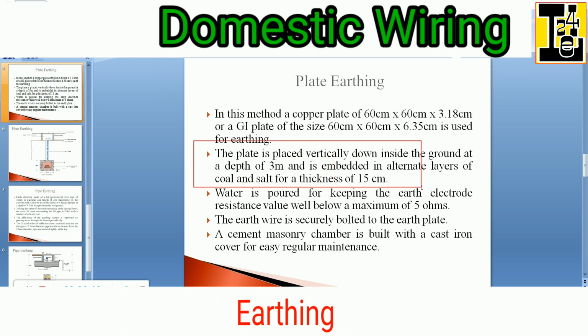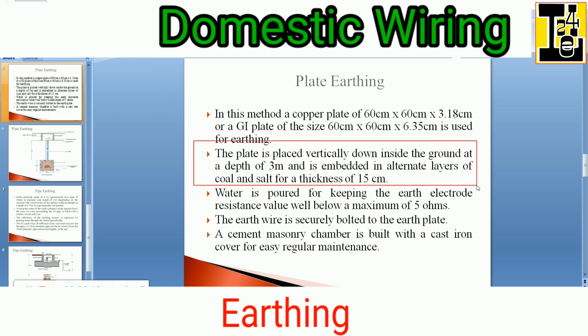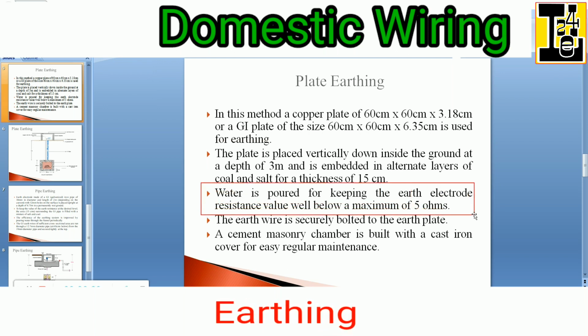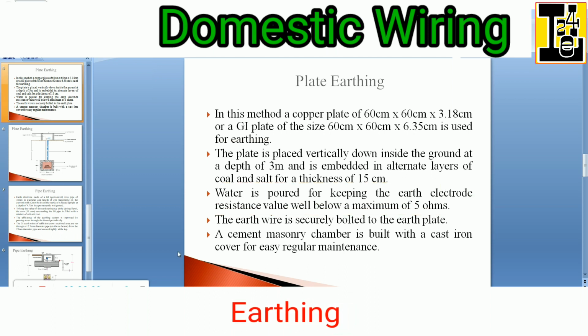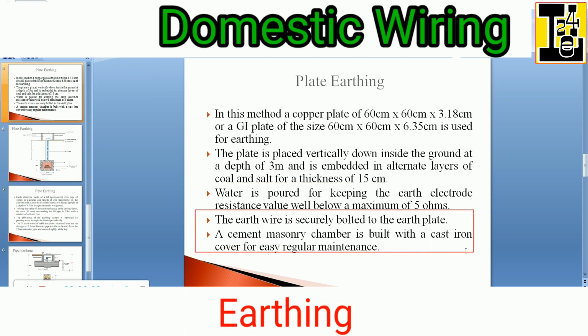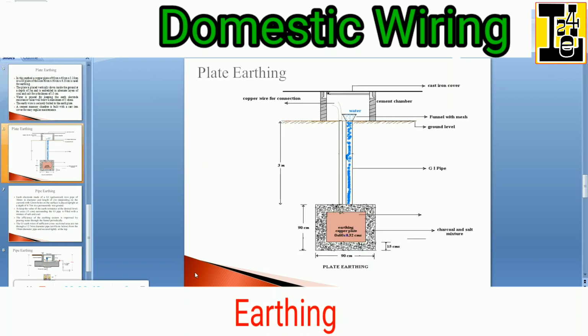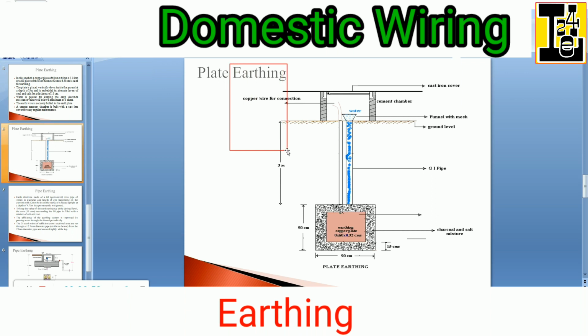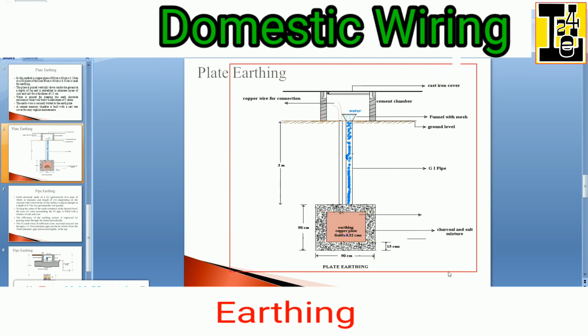The plate is placed vertically down inside the ground at a depth of 3 meters and is embedded in alternate layers of coal and salt for a thickness of 15 centimeters. Water is poured for keeping the earth electrode resistance value well below a maximum of 5 ohms. The earth wire is securely bolted to the earth plate and a cement masonry chamber is built with a cast iron cover for easy regular maintenance. So this is the plate earthing arrangement. You can observe as per the explanation.